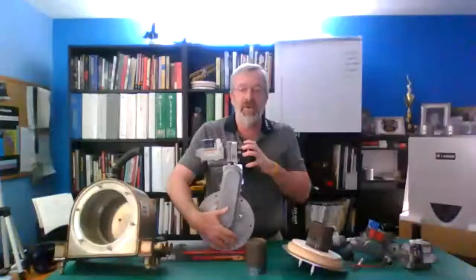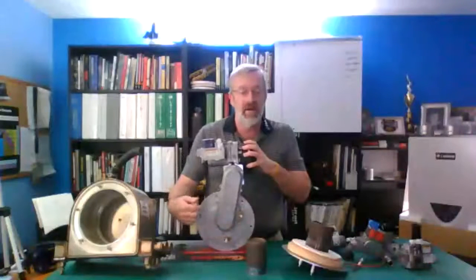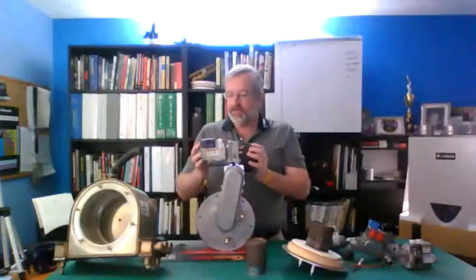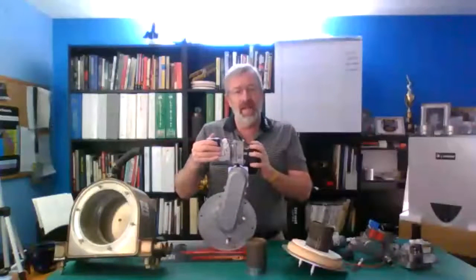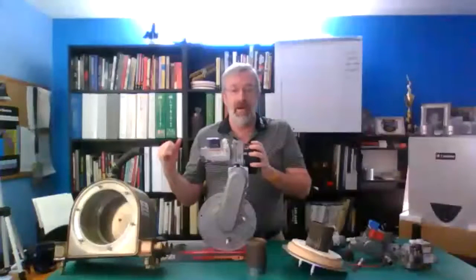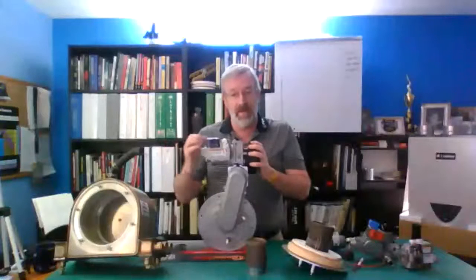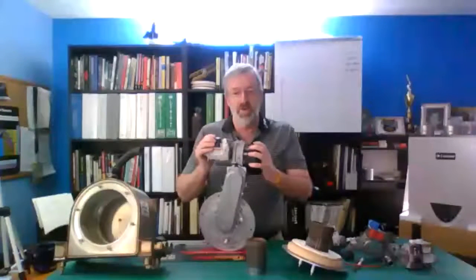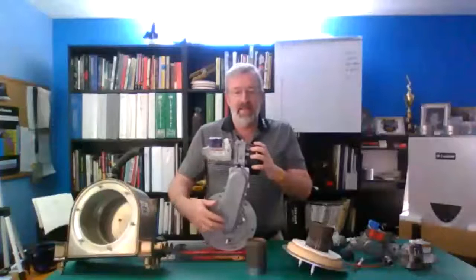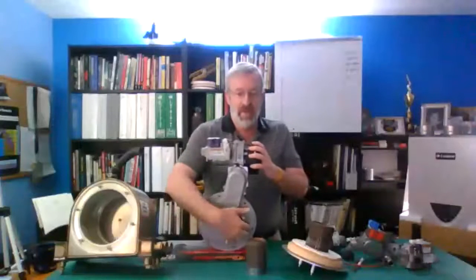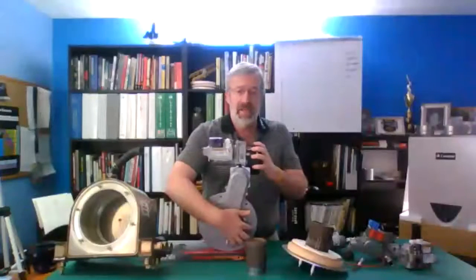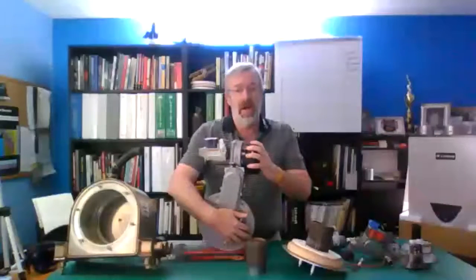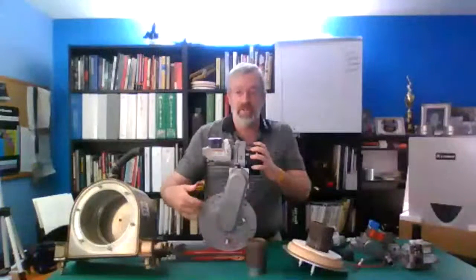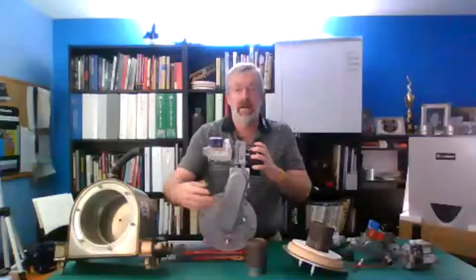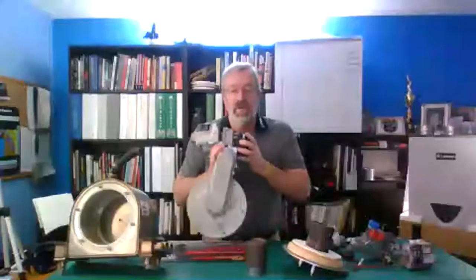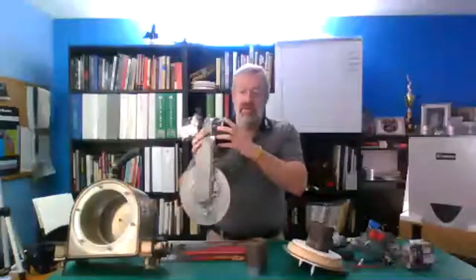Now loosen them all first and do it in a star pattern. What can happen is, let's say I put this boiler together and I didn't do a good job of putting a backer on my gas pipe coming in, and I put some torsion on it. As I'm taking these studs off, if I'm left with maybe this one here and I haven't loosened it, I'm going to put all the pressure on that one. So loosen them all up first, do it in that star pattern, then take them off. And then once you do, you're going to disconnect this from the front.